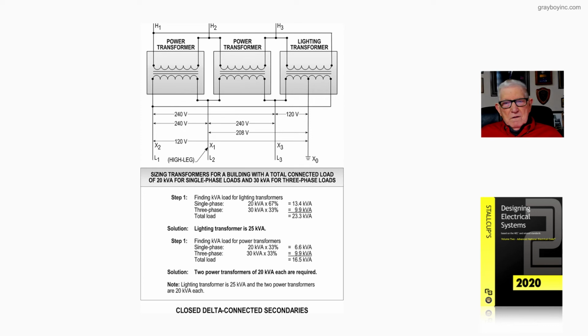That's your solution for finding the lighting transformer, which we would select at 25 kVA using the Acme chart for their particular size transformers. Now, step 1, we want to find the 2 power transformers. So it's just basically taking 1/3 of each load. So we take 20 kVA at 33%, 30 kVA at 33%, and we total those 2 loads, we come up with 16.5 kVA. Now we could move up to a 20 kVA, so we'd have 2 20s there, and we'd have a 25 for the lighting transformer.